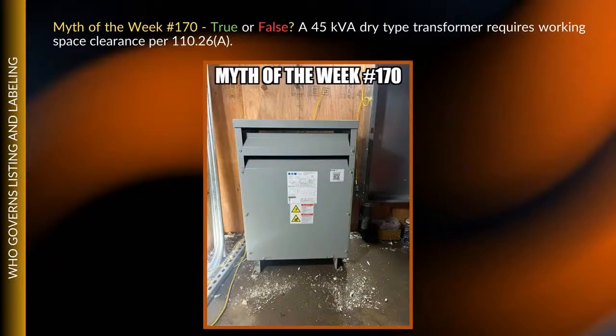Are you ready to move on? Go ahead—whether it's energized or not, that's the key. A lot of people say 110.26 only applies to energized equipment. That is one hundred percent wrong. This section doesn't say anything about whether the equipment is energized or not. It says you've got to be able to operate it safely, and maintain it safely, even if it's shut off.